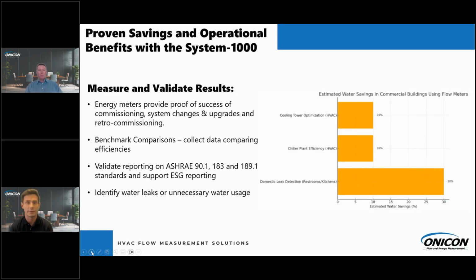In fact, there was a pilot project in Norway that emphasized the importance of energy metering. They had a project that showed you can save up to 10% by monitoring your BTUs, and their goal was only 3% across many campuses. Additionally, you can benchmark a true apples to apples comparison. We all know how you benchmark buildings. It's prior months to prior years, utility usage, but that doesn't always create the full picture. With the System 1000, you can bring all your utility meters in. You can see your output BTUs, energy efficiency from all your systems. And now you can get a true apples to apples comparison of how your system should be operating all year long. And as we mentioned before, it does support validating, such as ASHRAE 90.1 and 183. But on top of that, also 189.1, which is for energy efficiency and water usage.